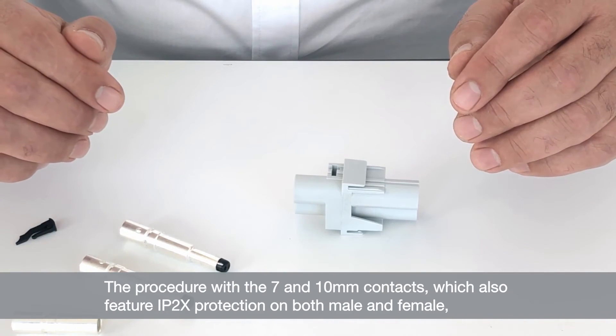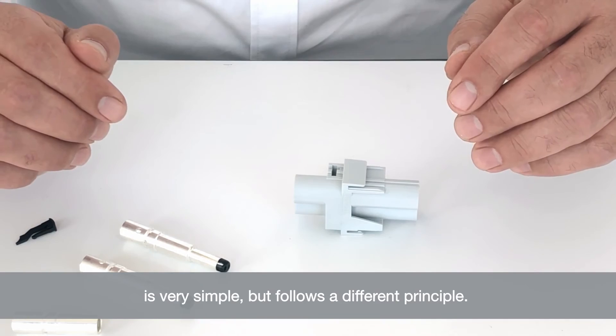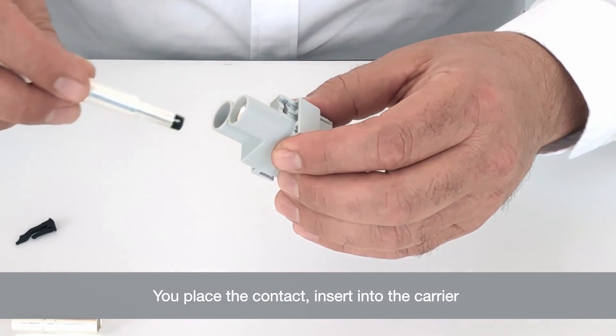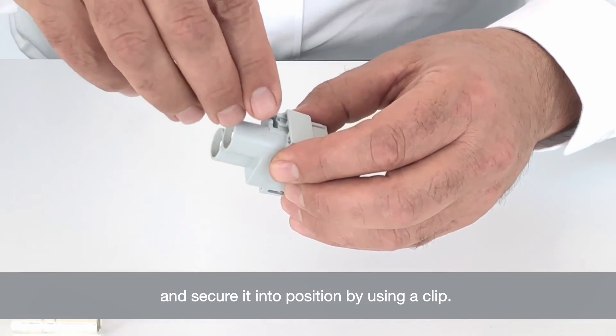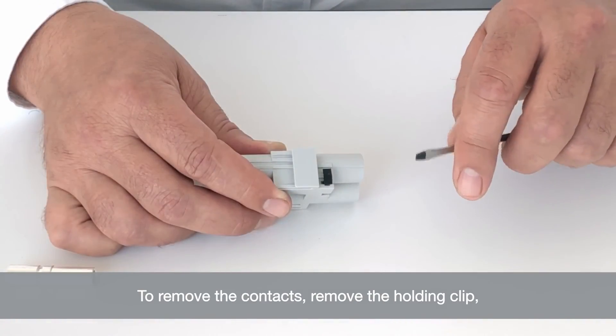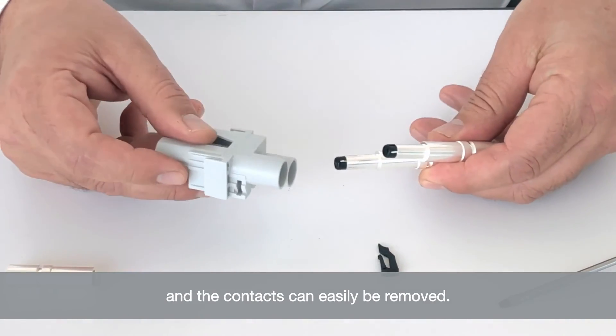The procedure with the 7 and 10mm contacts, which also feature IP2X protection on both male and female sides, is again very simple but follows a different principle. You simply take the contact, insert it into the carrier, and secure it into position by using a simple clip. Click into position and that is secured. To remove the contacts, you simply remove the holding clip and the contacts can easily be removed.